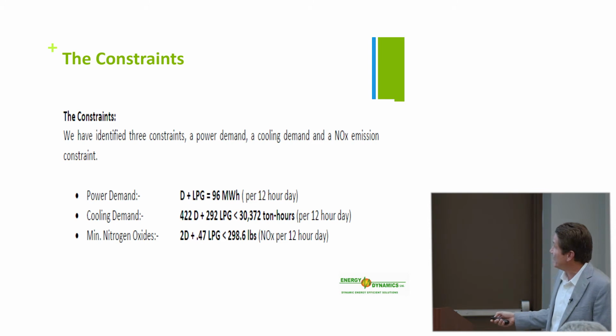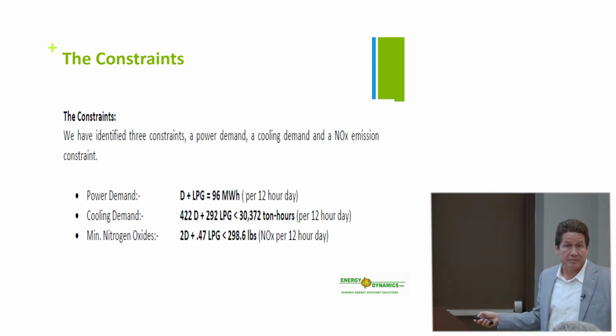And then the power demand, diesel plus LPG, is 96 megawatt hours - that's what they want in a 12-hour day. Cooling demand: 422 tons times diesel plus 292 tons for LPG is less than 30,372 ton hours for a 12-hour day.